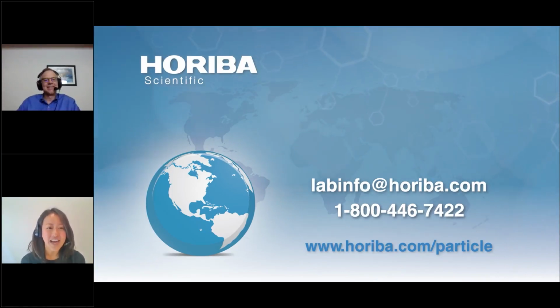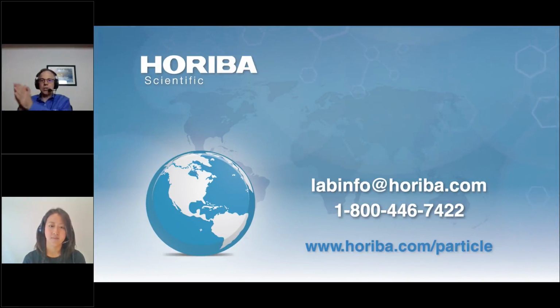Sure. If you begin the method development with one RI, and later you change the RI to get a reproducible result, what information do you get from it? Okay, so if you change your RI, you're not changing your repeatability. If I run a sample with one RI, I get 1 micron, and I change the RI, it shifts to 2 microns. It's just going to change all the numbers over. It's not going to affect repeatability. So the RI is really telling the math what light is doing inside the particle.